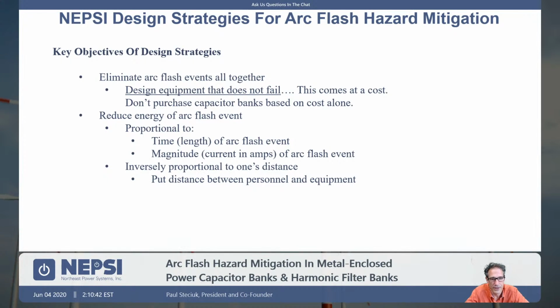So when you purchase capacitor banks, think about cost. Are you going to go with the low cost supplier, one that might be looking to reduce component costs, reduce voltage margins on their components, or do you go with a higher cost supplier, one that is doing testing, one that's increasing the ratings, one that is striving to reduce the possibility of equipment failure? If you can eliminate the failure within the component, within the ratings, within the system itself, you eliminate the arc flash event, and this is key. Eliminating arc flash events should be a desirable objective in any design.